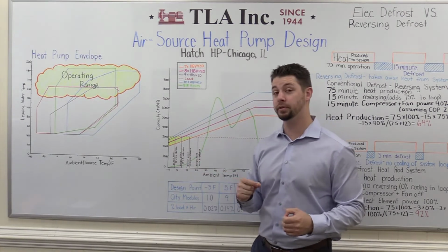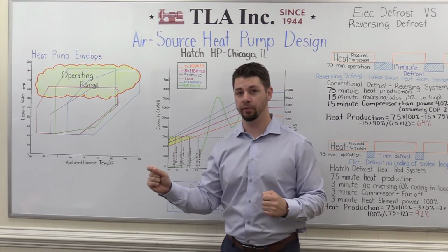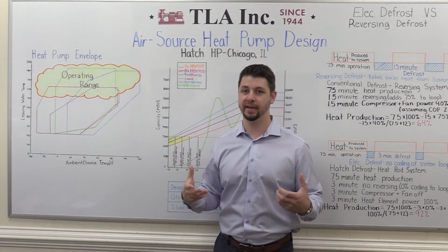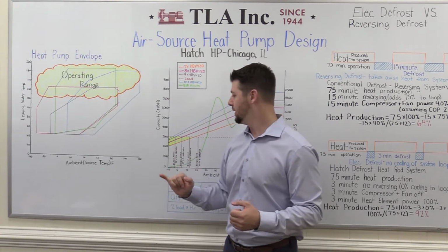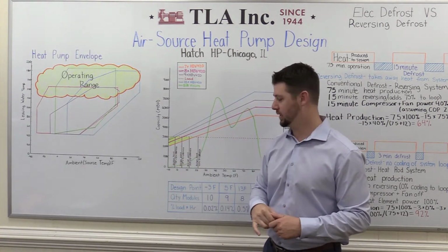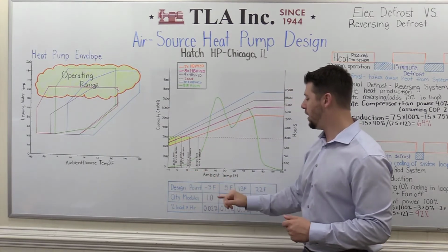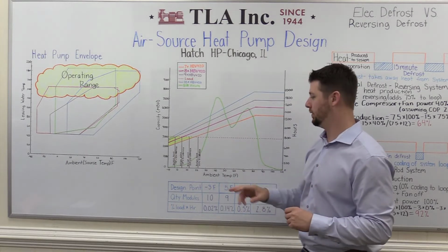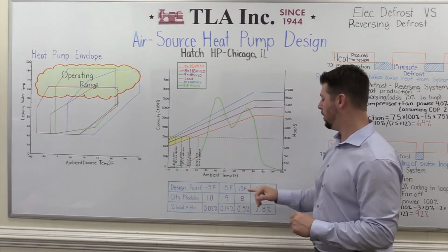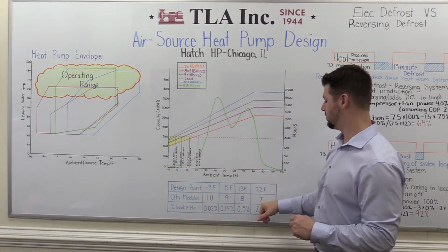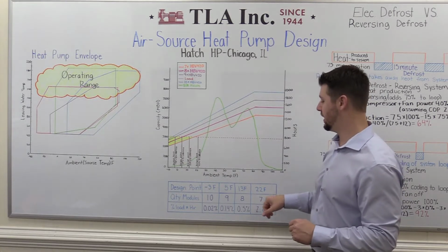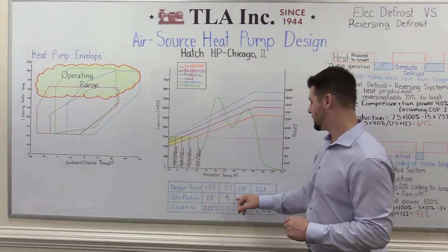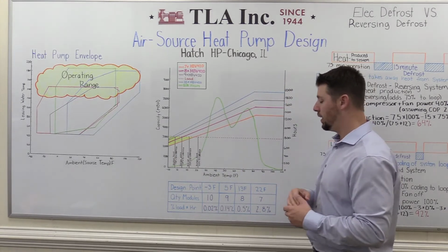So what we do to actually achieve a greater coefficient of performance, a more economical approach to solving heating with air source heat pumps, is to not design for this 1% condition. If we move out and get to this knee in the curve, what we call the knee in the bin data, what we see is that we can design around a 2.8% condition in terms of amount of hours per year, and we can drastically reduce the number of heat pumps we need.